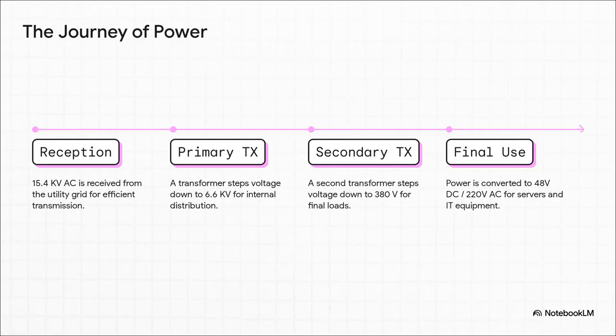So, before that power ever even reaches a server, it has to go on a bit of a journey. It shows up from the grid at a really high voltage. In this case, we're talking 15,400 volts, which is great for traveling long distances. But then, a series of transformers have to step that voltage way, way down to make it safe and usable for all the delicate electronics that actually run our digital lives.